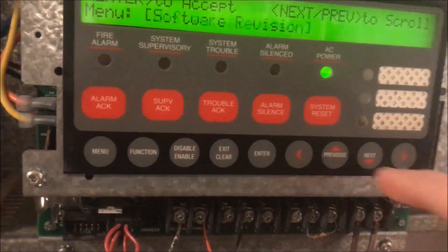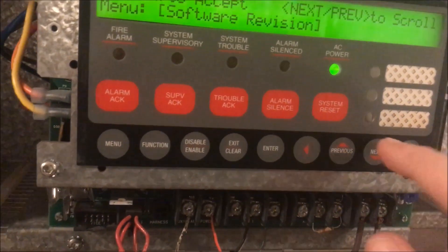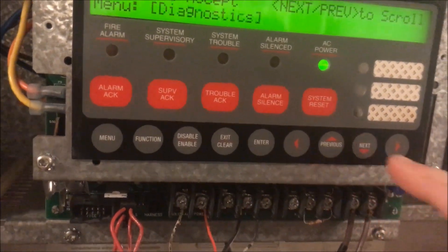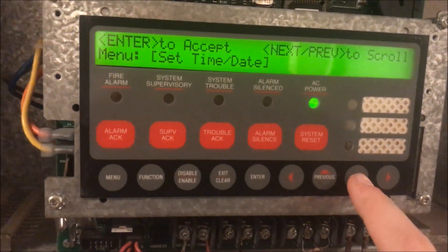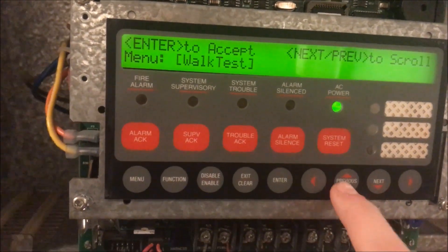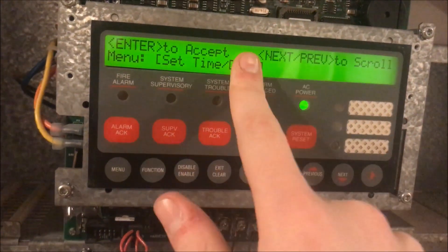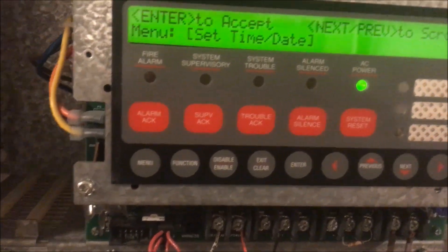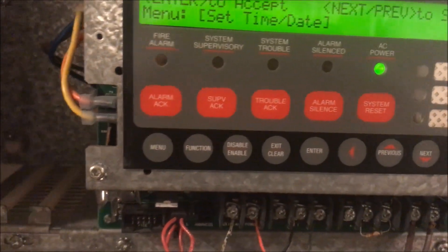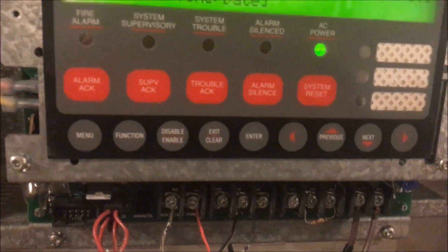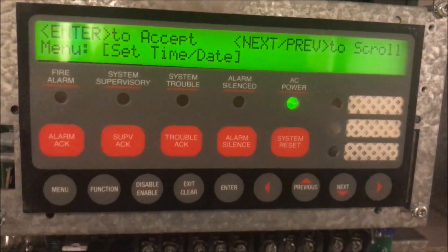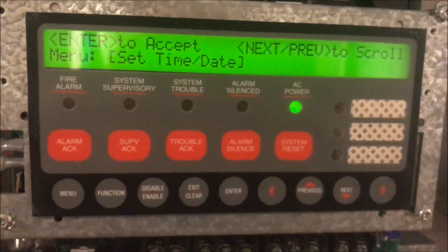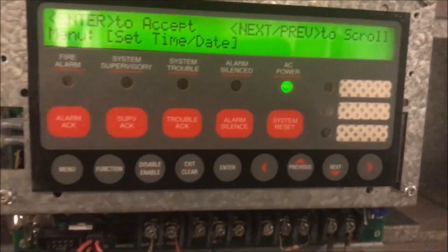Back in the menu, other level three options include: control view points, login/logout, view your logs, view your software version, view diagnostics, and set date and time — that's a new one. After a cold start, the panel loses its time, so you need to log into level three to set the current date and time, otherwise you'll have a trouble condition.